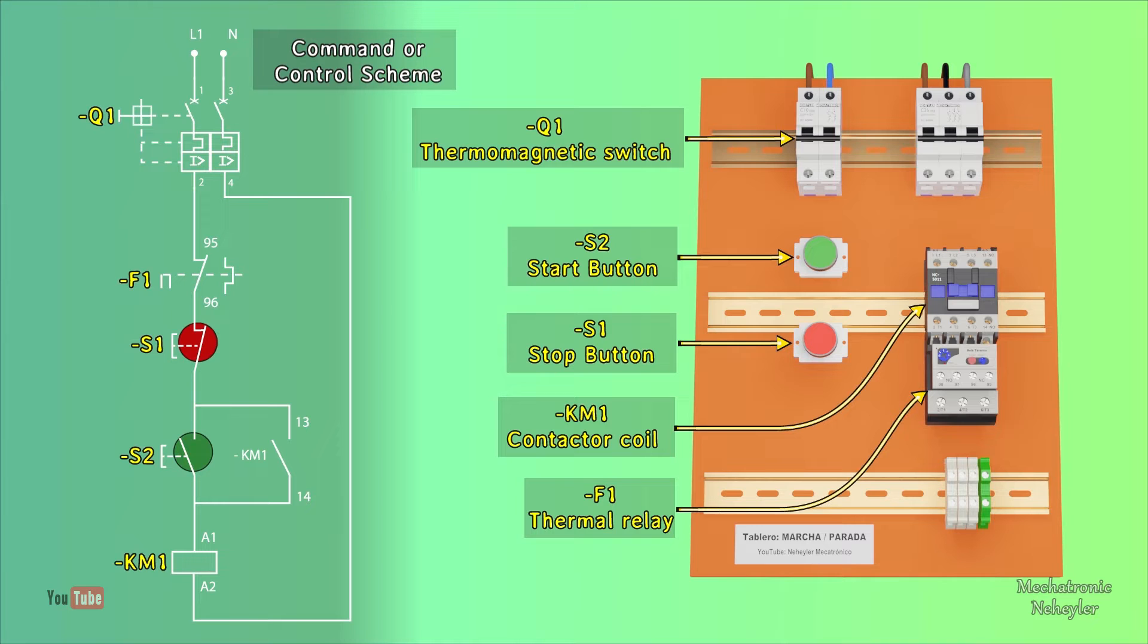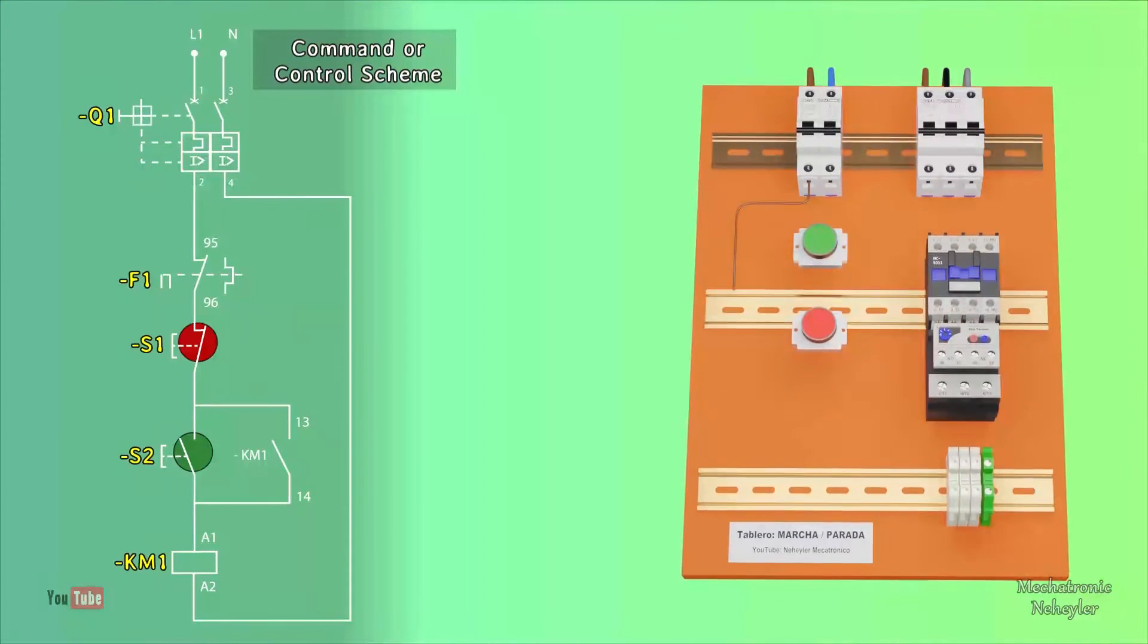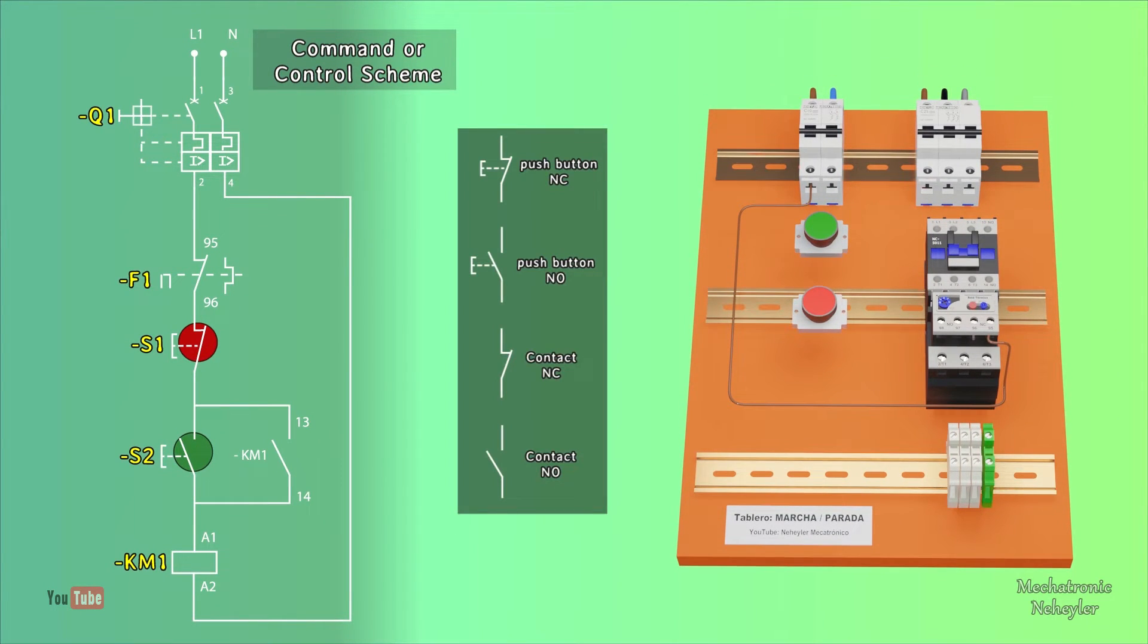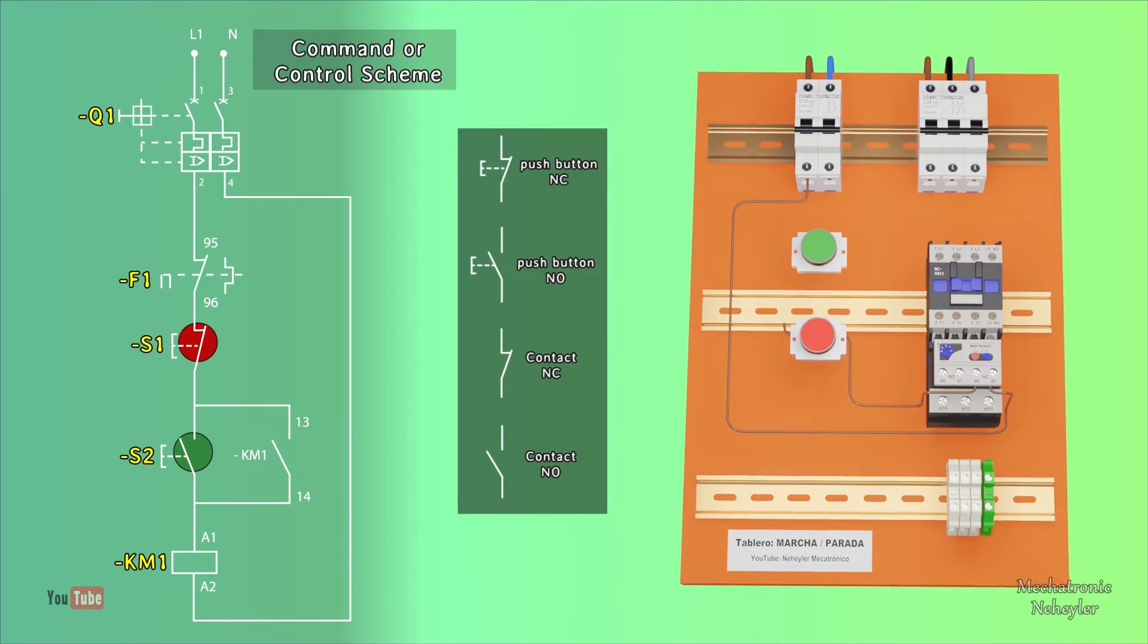For the wiring, we are going to be guided by the following scheme. The phase cable is taken to terminal 95 of the thermal relay contact and from terminal 96 it is taken and connected to both buttons and then to terminal A1 of the contactor coil.